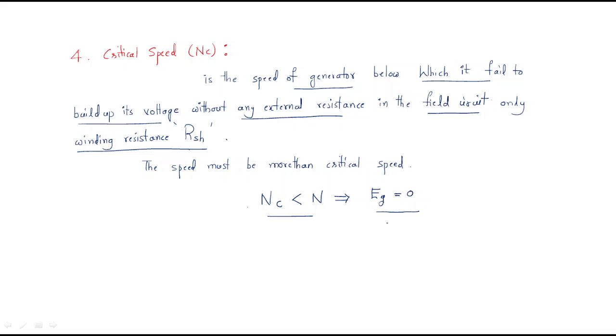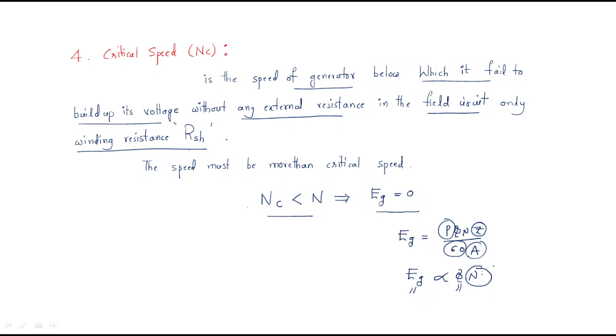Why must the speed be high? Generally, the generated EMF formula is: EG = P·Φ·N·Z / (60·A). Here P, Z, and 60 are constants, and Φ is also constant, so the generated EMF depends on both flux and speed. If the speed is low, the generated EMF will become low. The speed must be more than the critical speed.